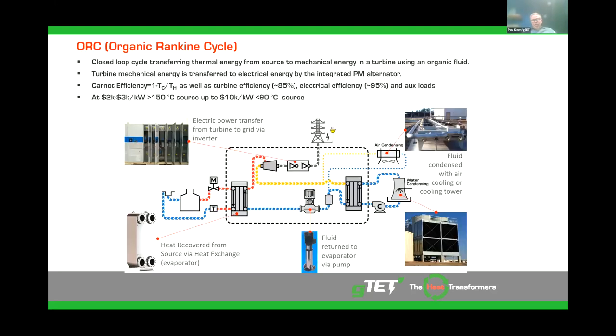I'll now discuss some of the thermal energy solutions that GTET can deliver to process the waste thermal streams. So the core technology for us, as I mentioned, is organic Rankine cycle heat engines. It's the most common and robust technology to convert low-grade heat into shaft power. ORC is a closed-loop cycle that transfers heat from the source into a low boiling point organic fluid via an evaporator or heat exchanger, in turn heating and pressurising the fluid to drive a turbine. The fluid is then condensed by transferring the residual heat through the cooling system before being accumulated and pumped back to the evaporator. As with refrigeration, condensing can be achieved by cooling towers, air coolers, adiabatic coolers, or as a secondary heat transfer process such as drying.